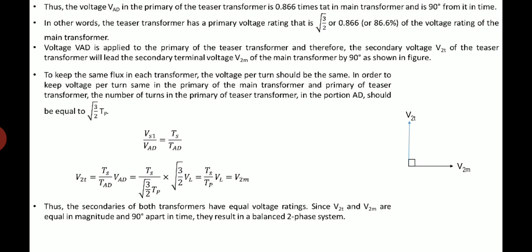In other words the teaser transformer has a primary voltage rating that is root 3 by 2 of the voltage rating of main transformer. The voltage VAD is applied to the primary of teaser transformer and therefore, the secondary voltage V2T of the teaser transformer will lead the secondary terminal voltage V2M of main transformer by an angle of 90 degree which is shown in this phasor diagram.